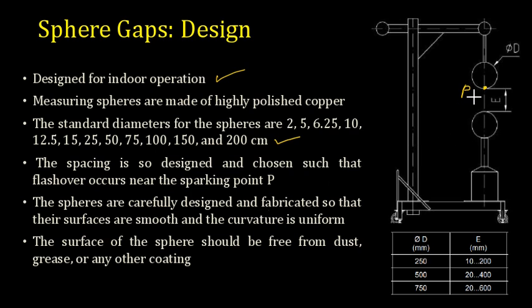It is designed so that you will have a flashover from this P to the second sphere. Now the sphere is to be kept very smooth. If there are any irregularities in the sphere, the field will not be uniform, and you will not get accurate results for the voltage measurement. So the surface of the sphere should be free from dust, grease, or any other impurities, and it has to be as clean as possible.